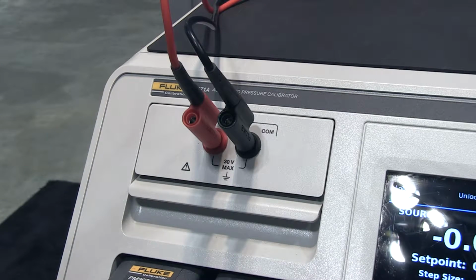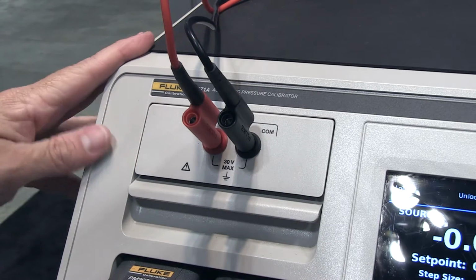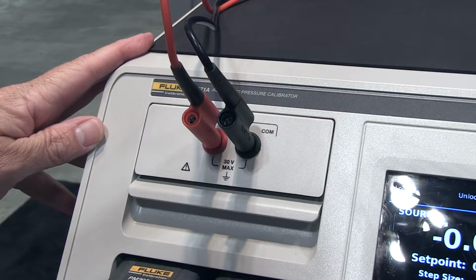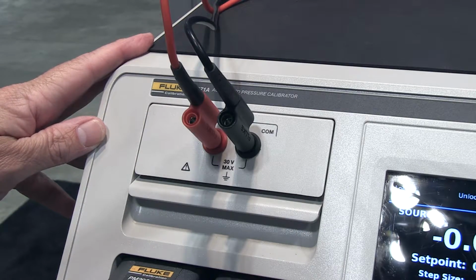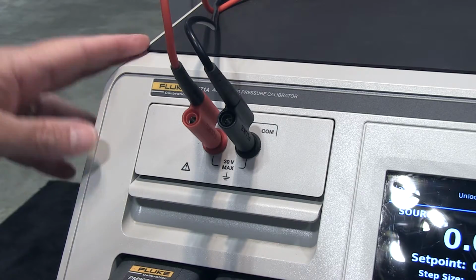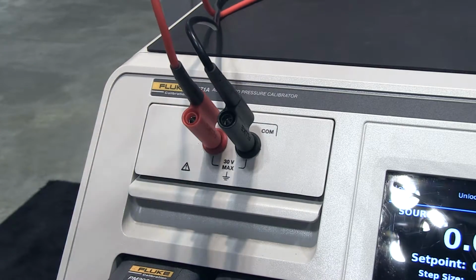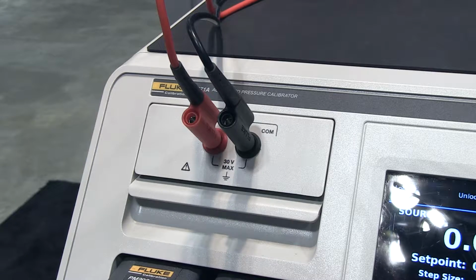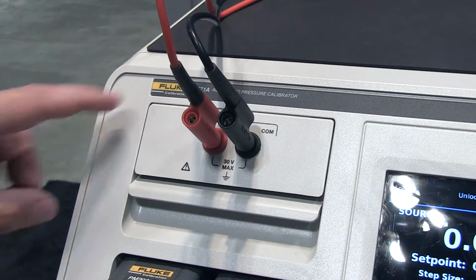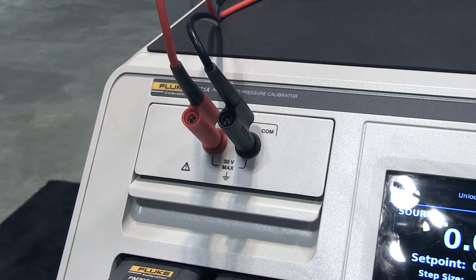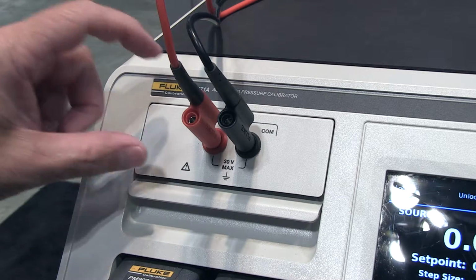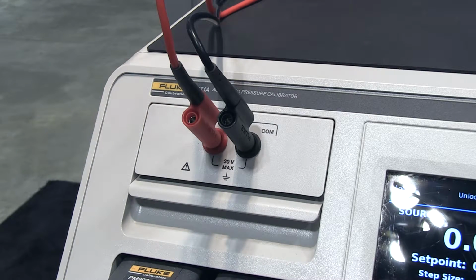Integral to all the 2271As is an electrical measurement module which handles 4 to 20 milliamps, 0 to 30 volts DC, and also is where you connect HART transmitters, and it has a built-in 250 ohm resistor for the HART loop. The EMM, or electrical measurement module, is a module, so it can be taken out of the calibrator, recalibrated. You could have spares on the shelf if you want to ensure that you have no downtime.